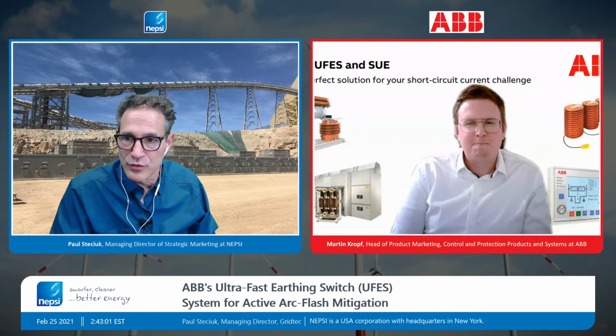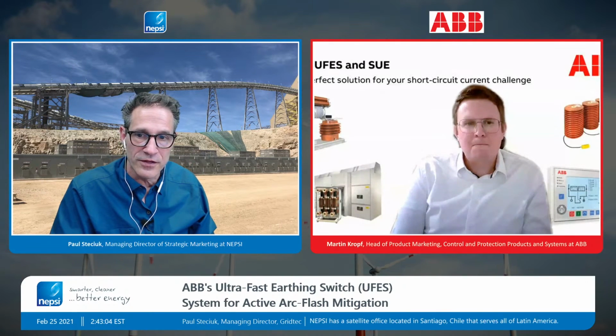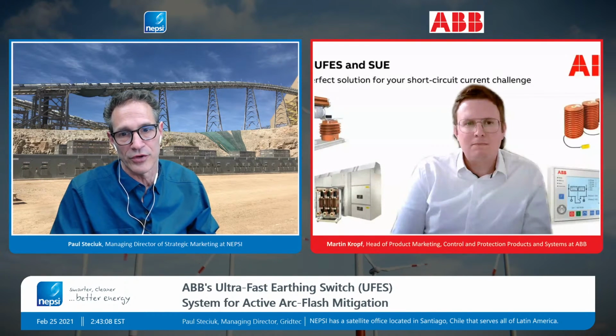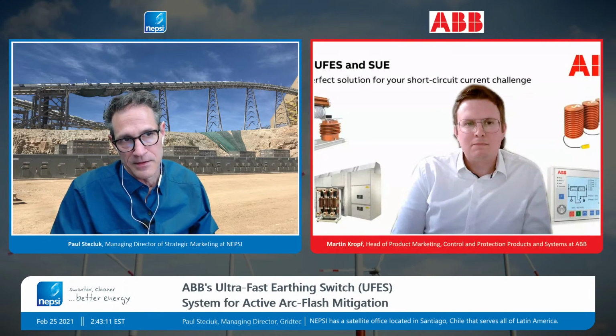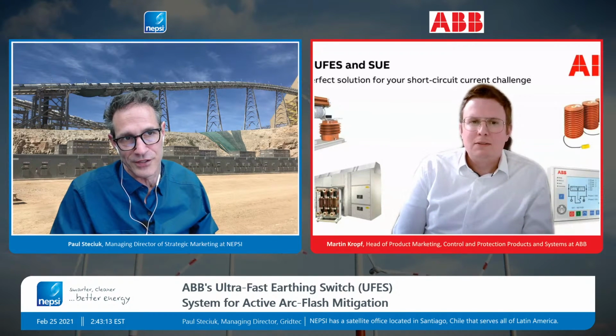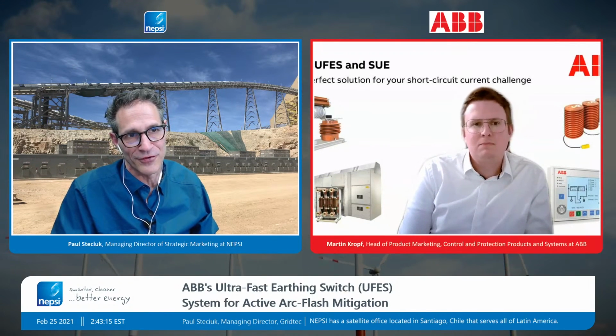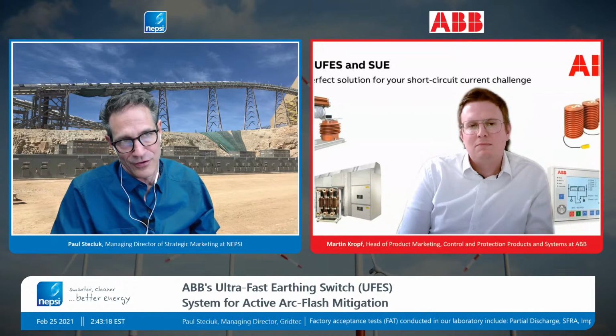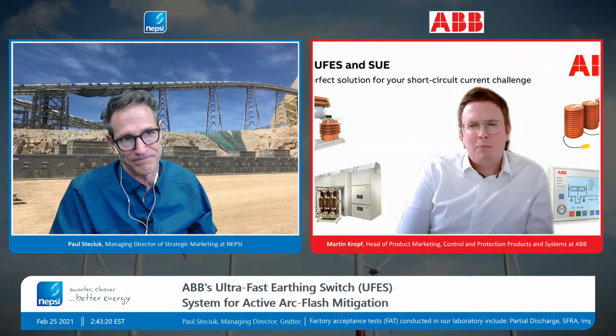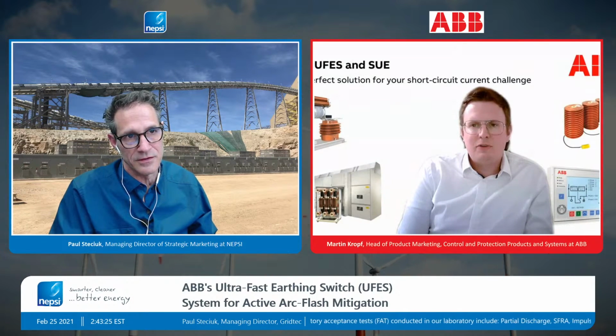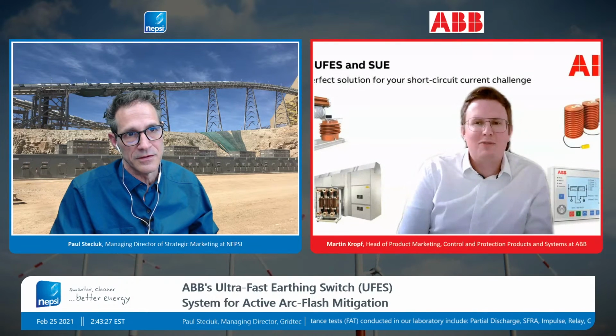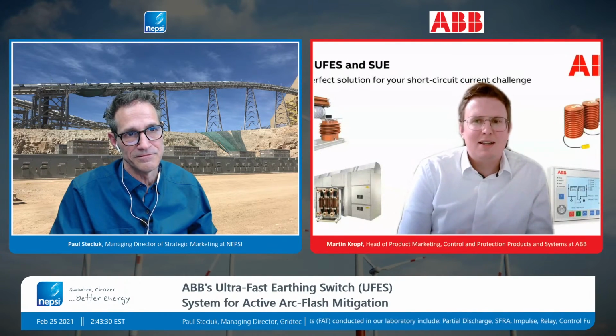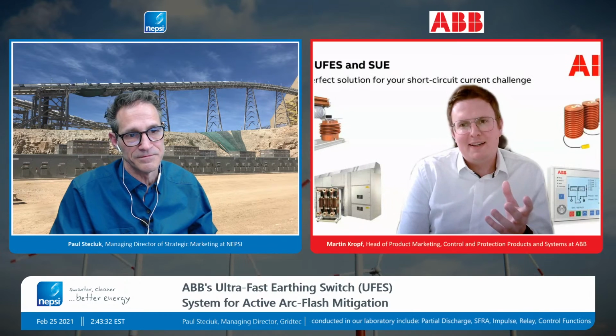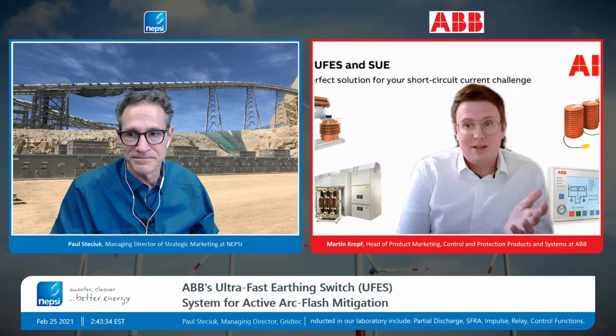Next question is, would you expect the UFES to prevent the operation of the bus differential relay by locally causing its associated breaker to operate first? So in other words, is the differential protection faster than the transfer trip associated with the UFES? I mean, the point is, yeah, this is a tricky one. The thing is that, first of all, how does differential protection really act to interrupt the fault?